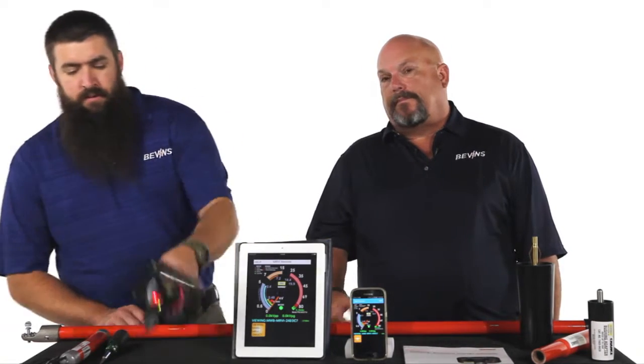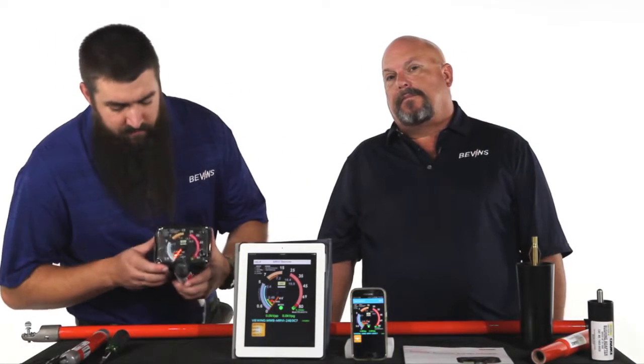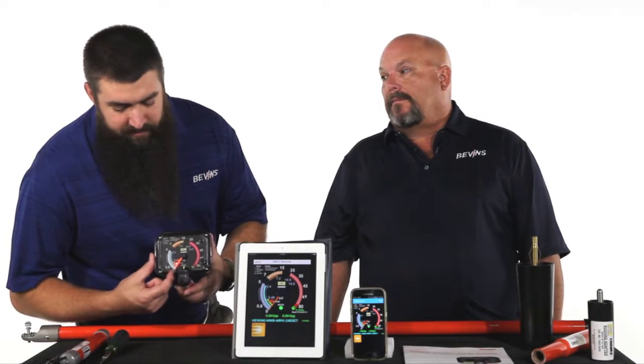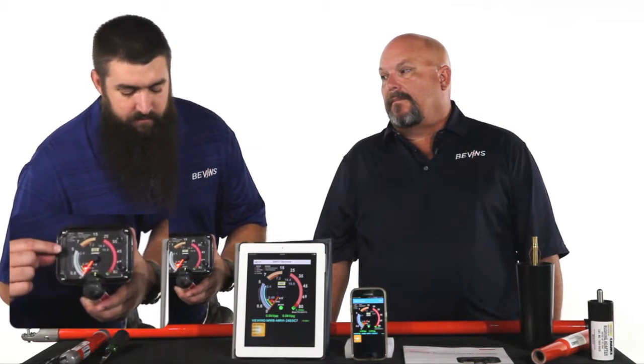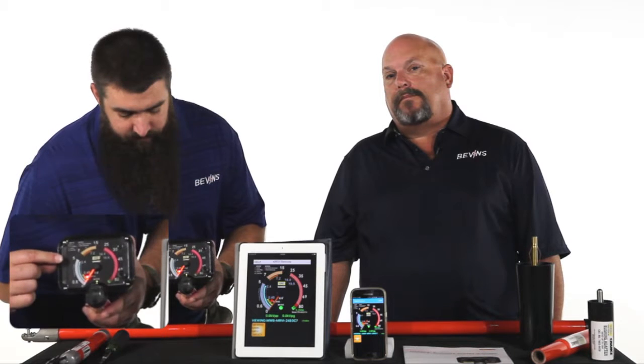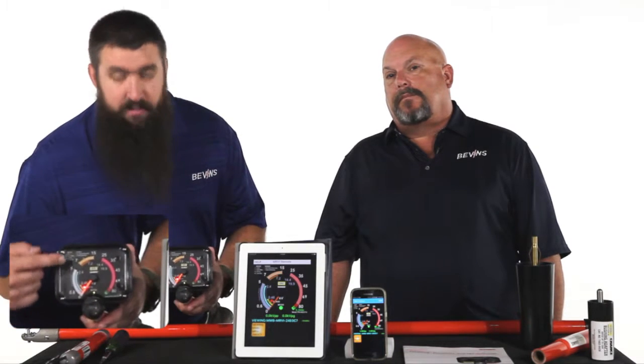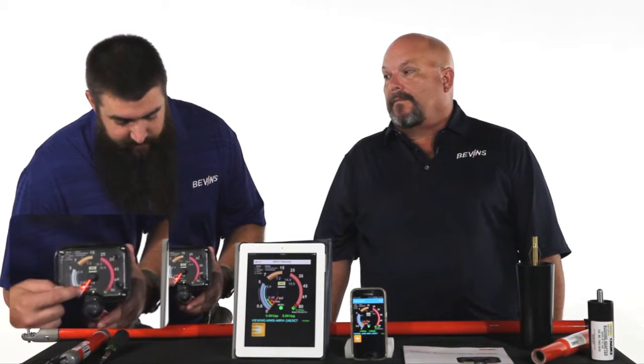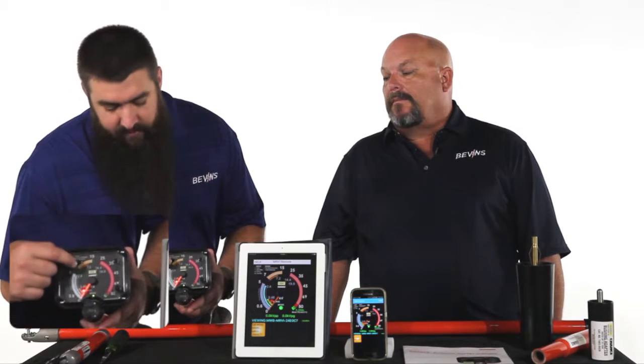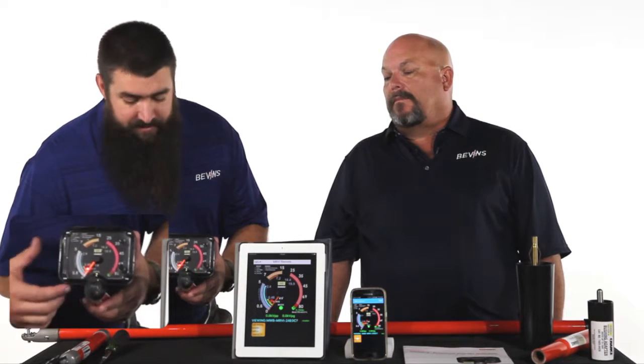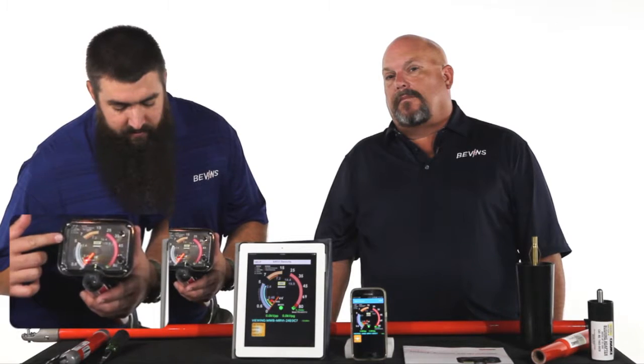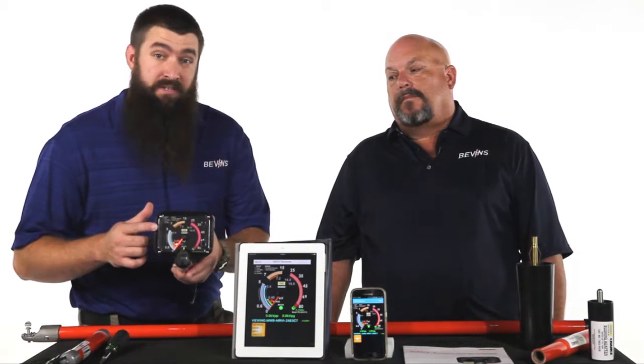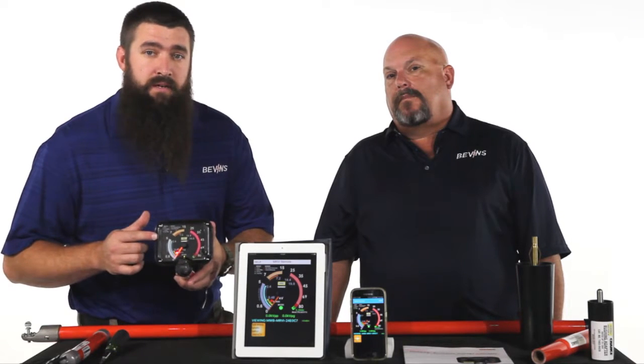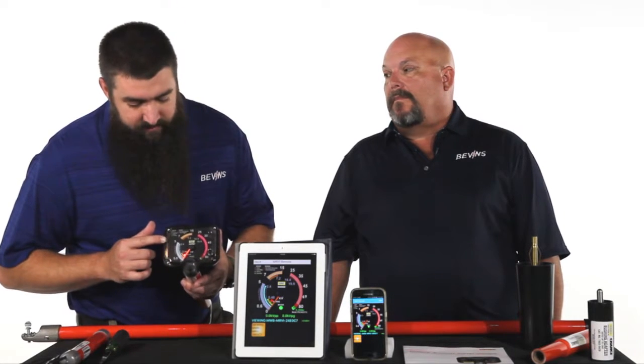Let's take them through the readings and what they mean. On the front dial face of the MARVI, the needle pointer points to the phase-to-phase equivalent voltage on the outer scale, or the phase-to-ground equivalent voltage on the innermost scale. As the needle pointer rises to a value, it points right to the voltage value in kilovolts that you're reading at the time.